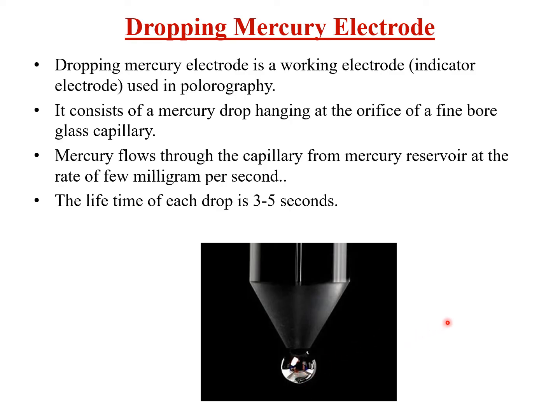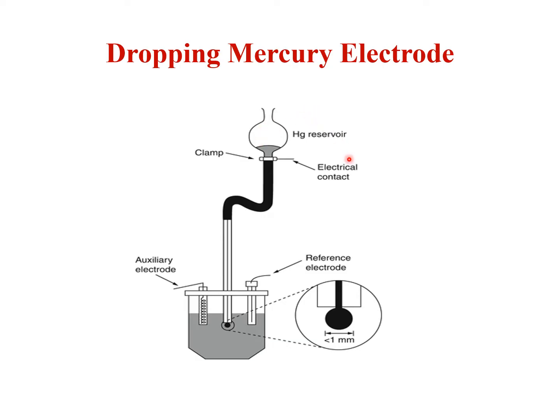Now we will see the construction and working of a dropping mercury electrode. There is a mercury reservoir connected to flexible tubing, which is then connected to a glass capillary. A mercury drop is formed at the orifice of this capillary at around three to five second intervals. The electrode is dipped in an analyte solution whose concentration is to be found, along with a reference electrode and an auxiliary electrode.